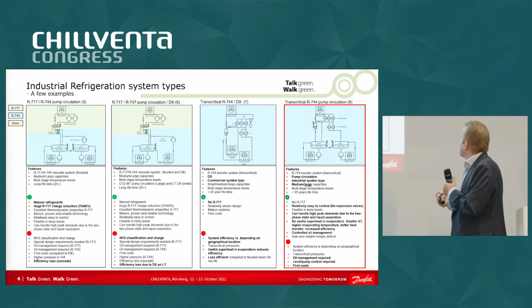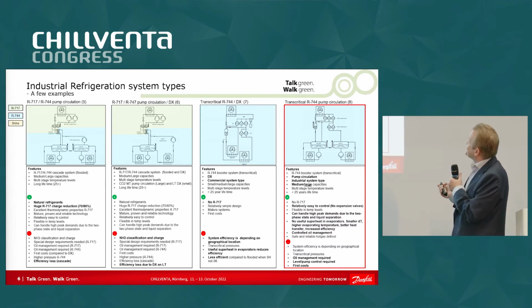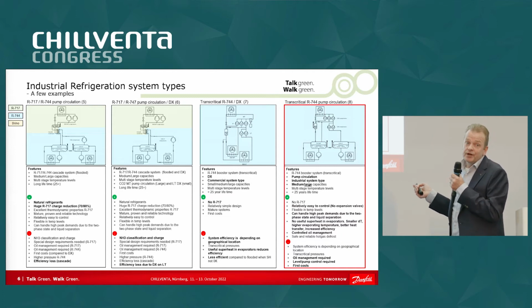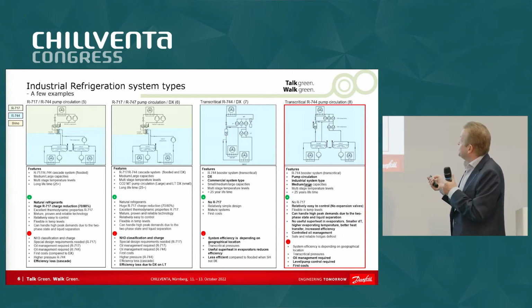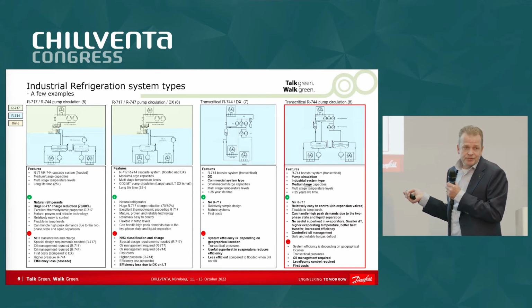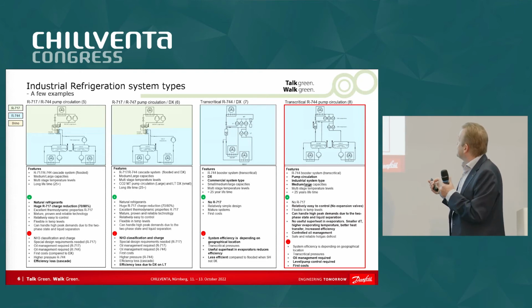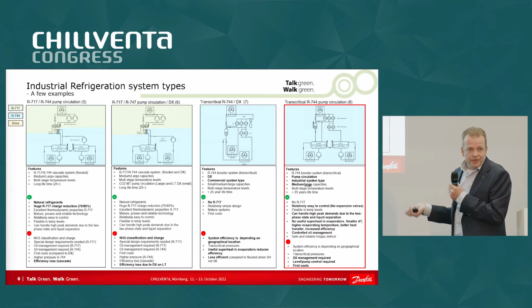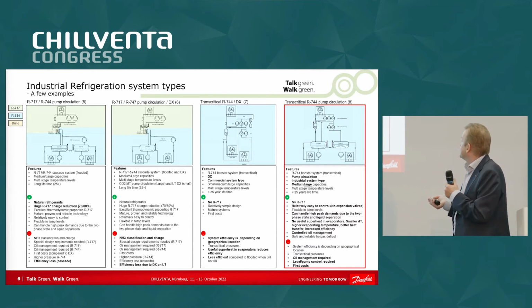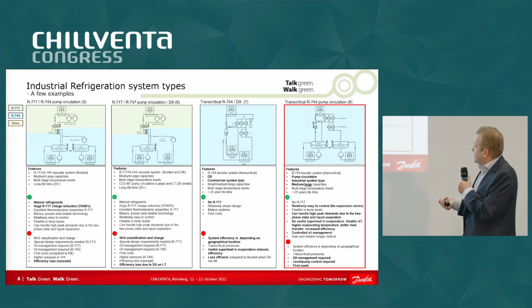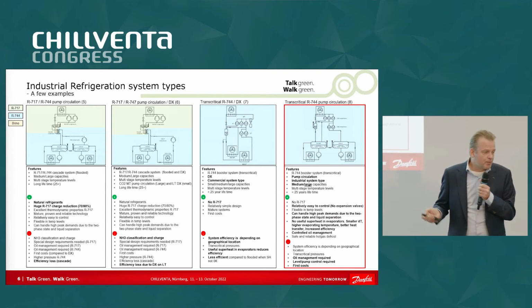But this one, it looks the same, but it is a transcritical cycle on top and an industrial flooded cycle here. And this could be a very interesting situation for larger systems because you have to imagine it could be 40, 50 evaporators, and then the system has to be robust and relatively simple. And this is relatively simple. You just have a pump, you open the valves, close the valve, and that's rock solid, I would say. But of course, the downside is you have to recover all the oil, so you need to rectify it. You need pumps, you need separators, so the first costs are probably higher.